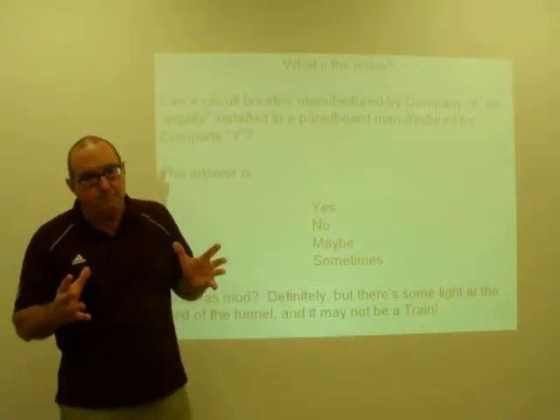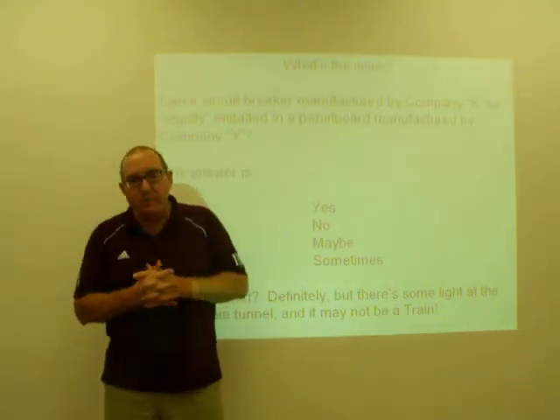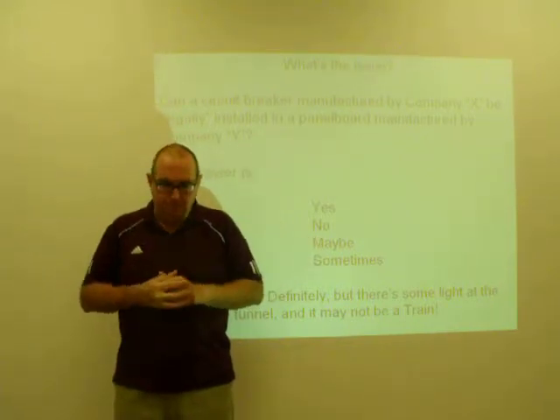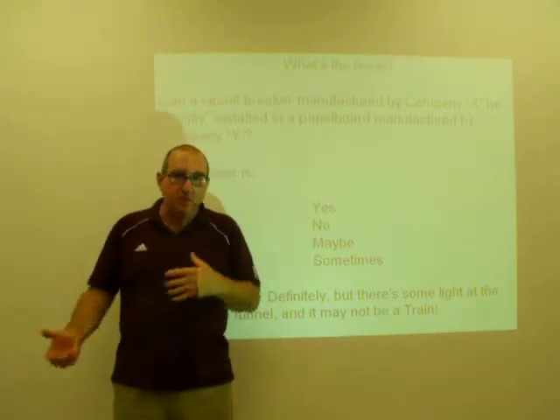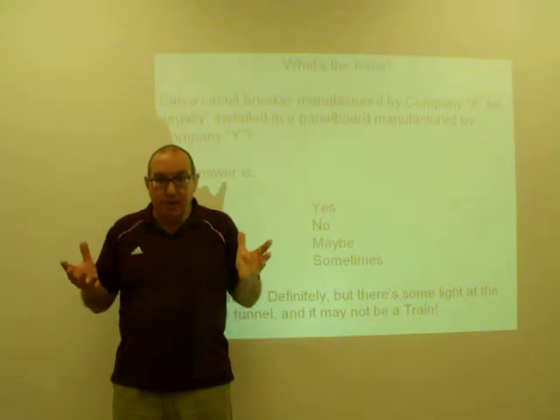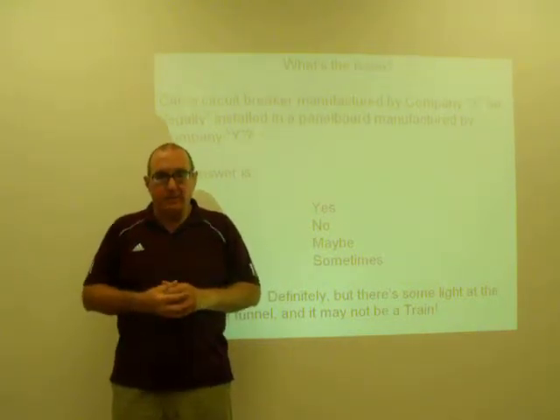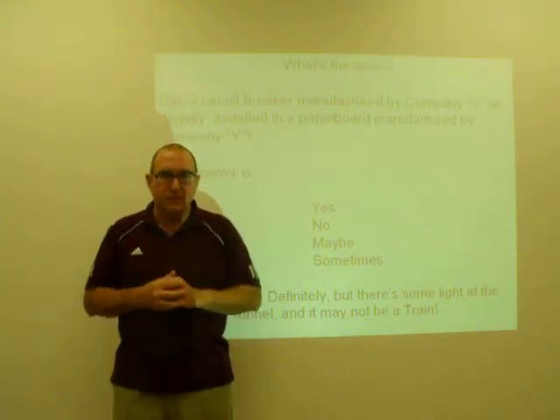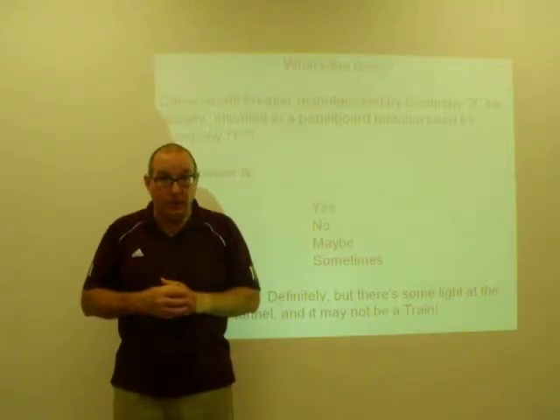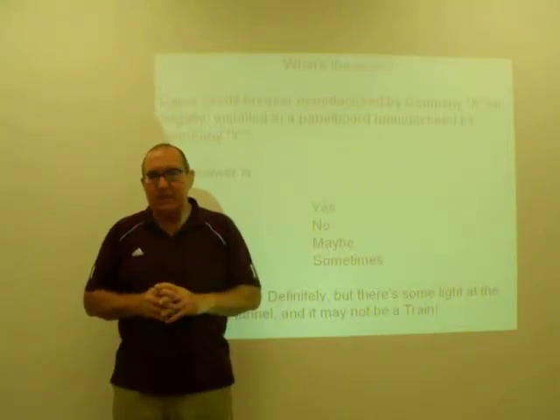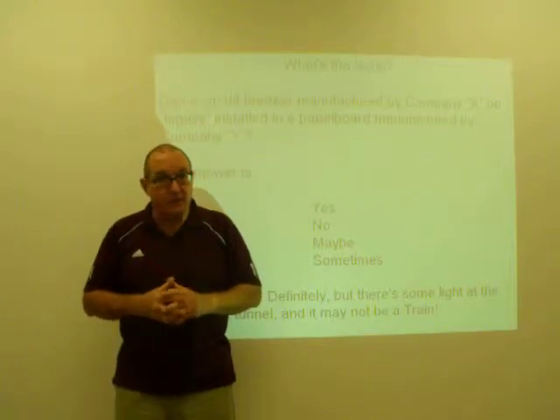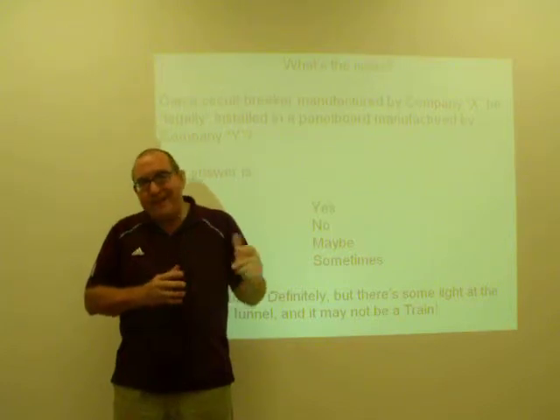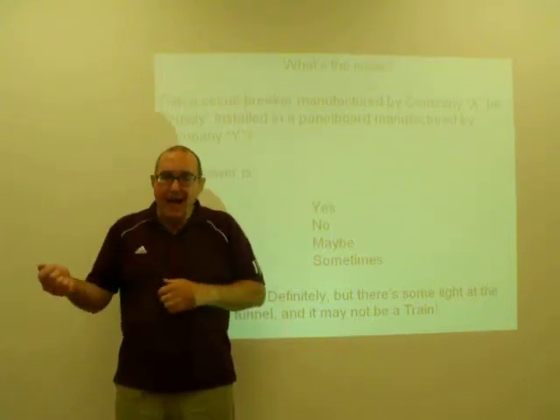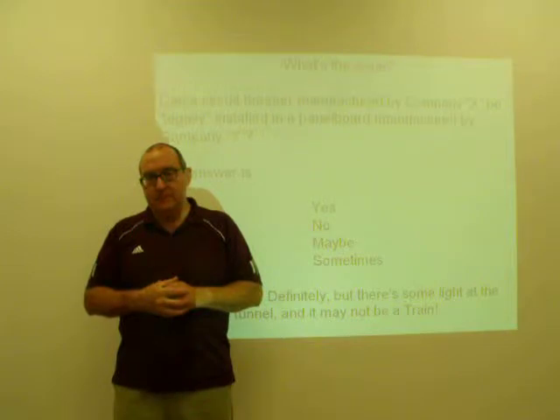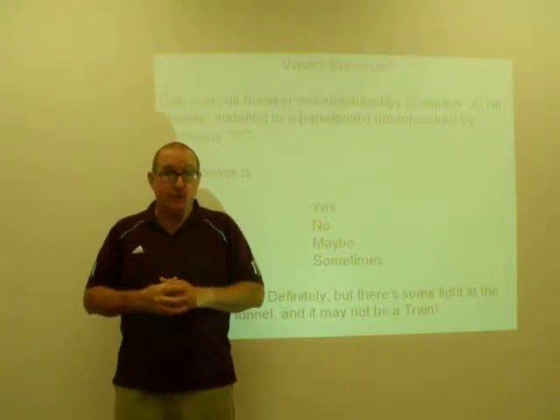What's the issue? Can I take a circuit breaker manufactured by company X, whether it be Square D or GE or Siemens or Cutler-Hammer or whoever, and install that breaker legally, in compliance with the National Electrical Code, which is not a legal document in that sense unless it's been adopted by your jurisdiction as a legal entity, the code? Can I install that brand X breaker in a brand Y panel board? Well, it's not a simple answer.